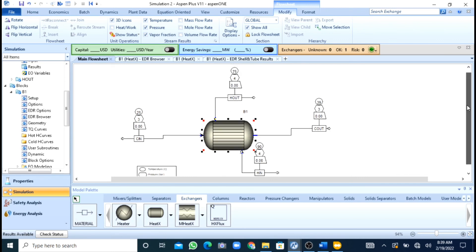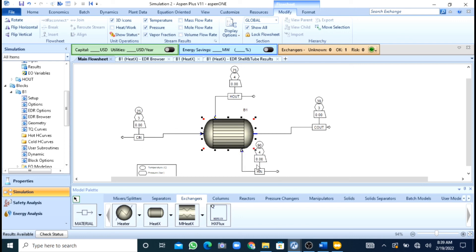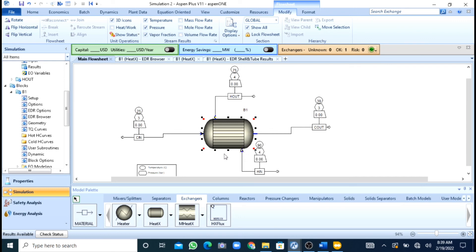You can see that the temperature has been reduced. In rating, we are evaluating our exchanger — our input was 90 degrees, we want our output to be 77 degrees, and then we rate the exchanger with respect to that specific requirement. But in simulation, our input values and our exchanger define the output values.